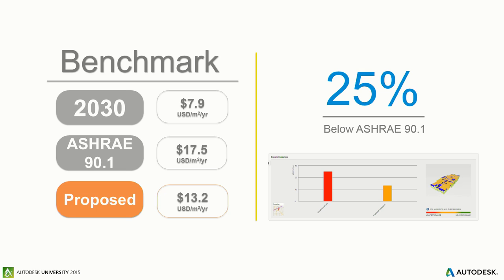Otherwise, if you get a number like 50% saving or 5%, that doesn't make sense anymore. So after you understand that the number makes sense, then you can start using the parametric information that you give to your electrical engineer or other engineers, so they have this target, and you can start a discussion. For example, in lighting, our target is 0.7 watts per square foot. You need to give that information before they design, otherwise after they finish the design, they cannot make adjustments anymore. And this determines what type of mechanical system makes sense with this target.